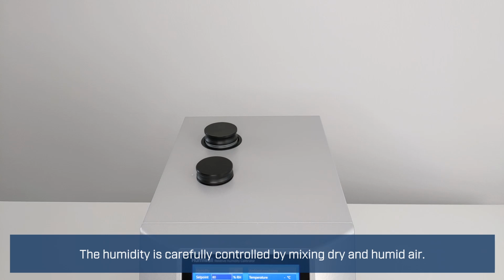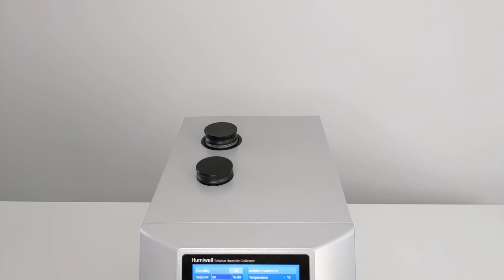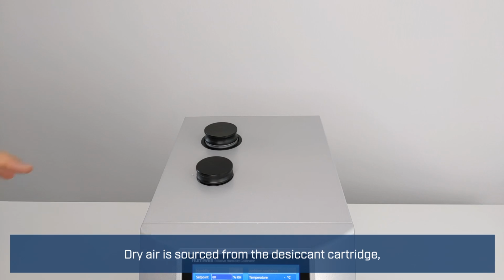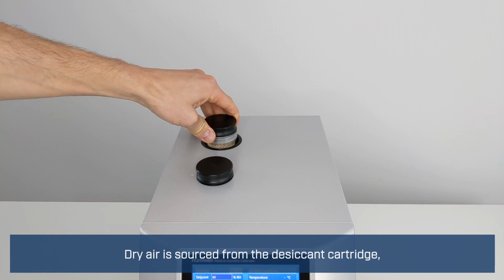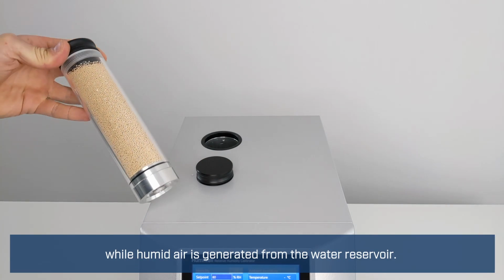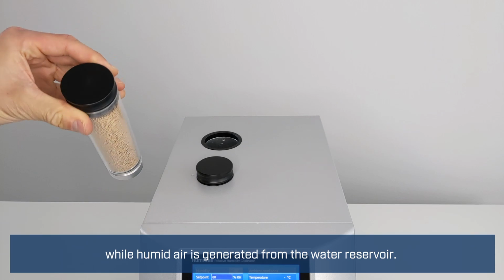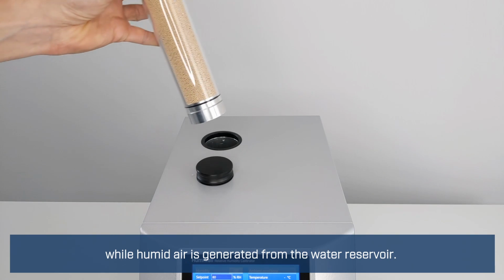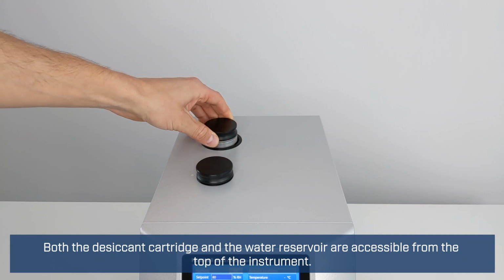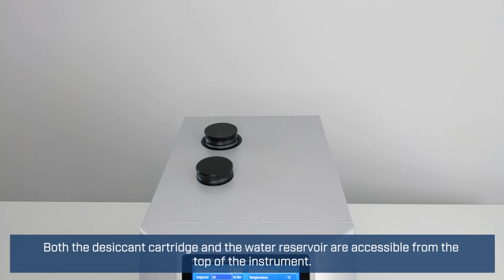The humidity is carefully controlled by mixing dry and humid air. Dry air is sourced from the desiccant cartridge, while humid air is generated from the water reservoir. Both the desiccant cartridge and the water reservoir are accessible from the top of the instrument.